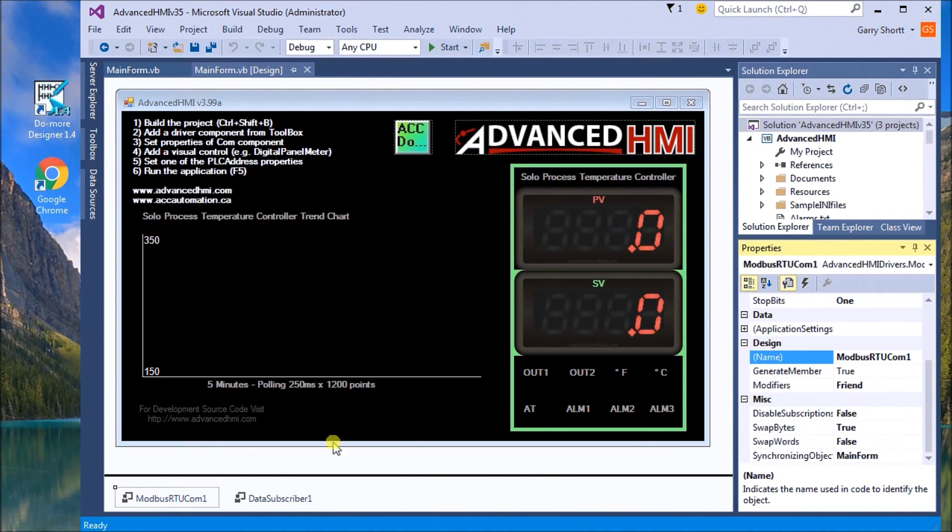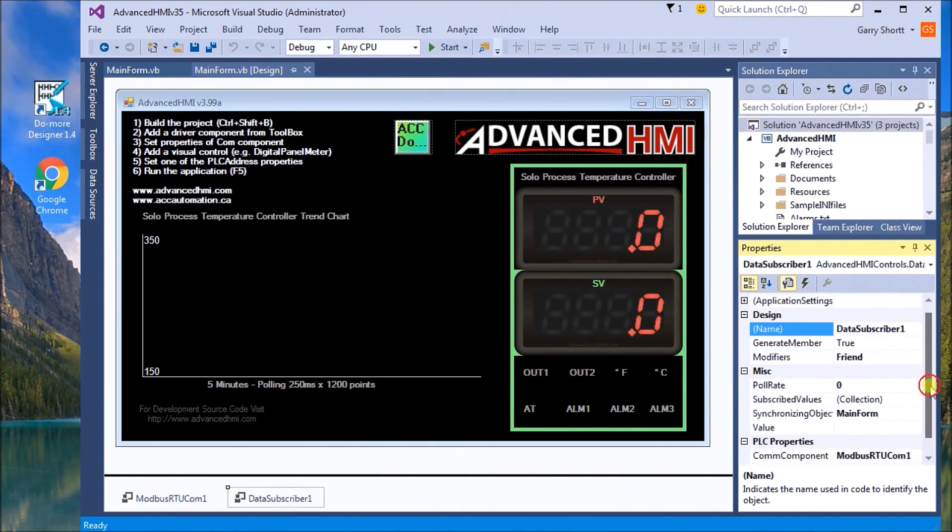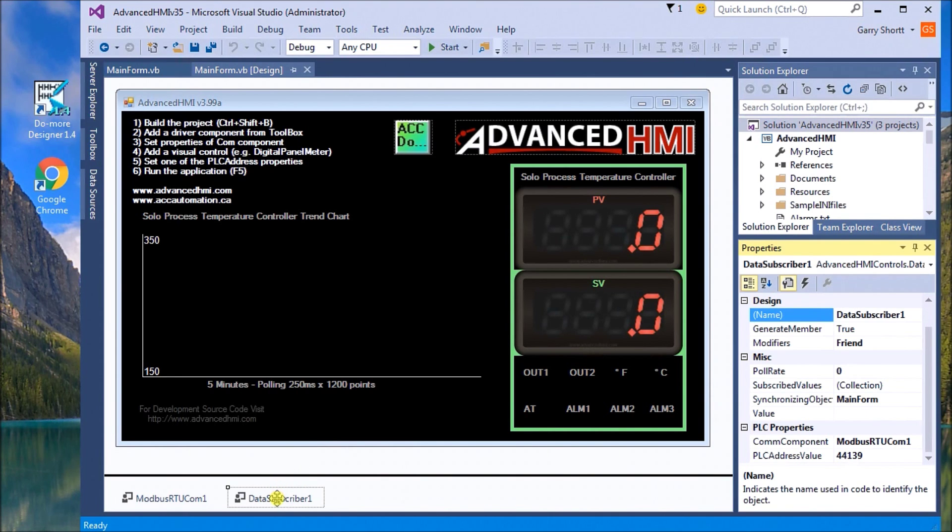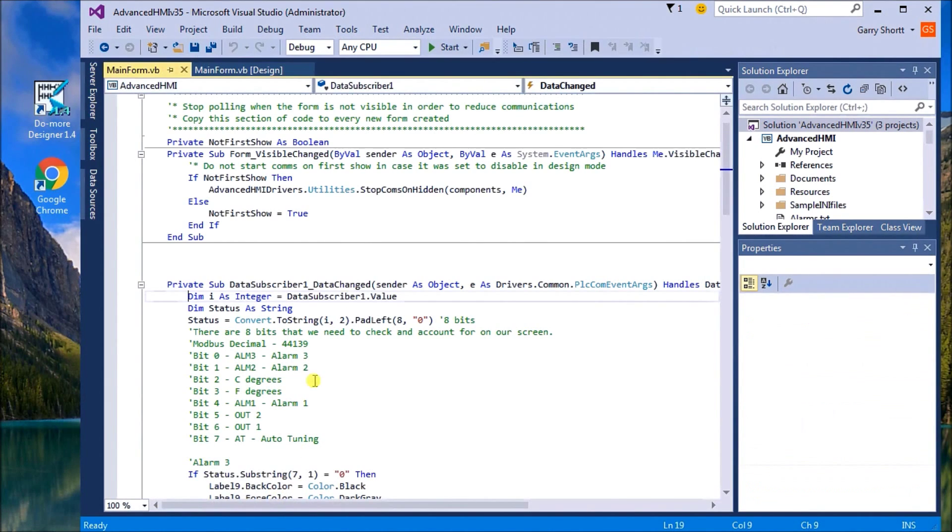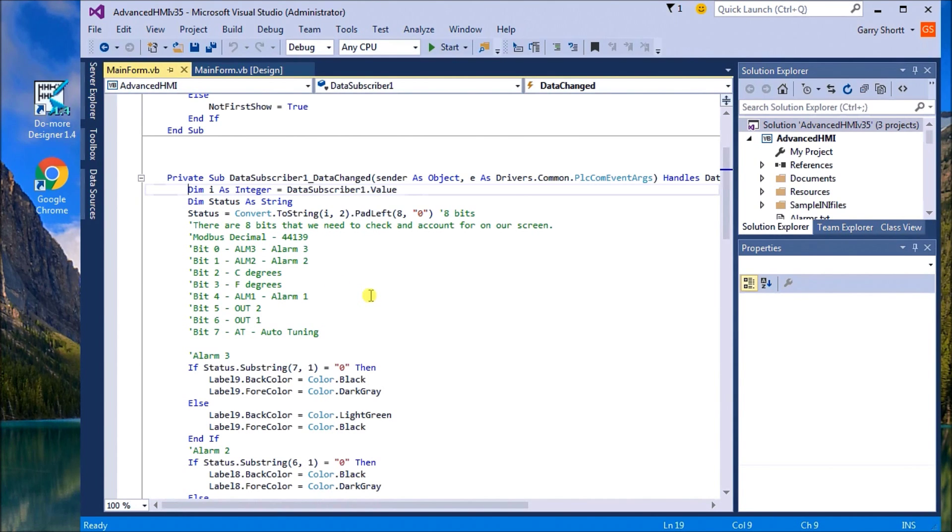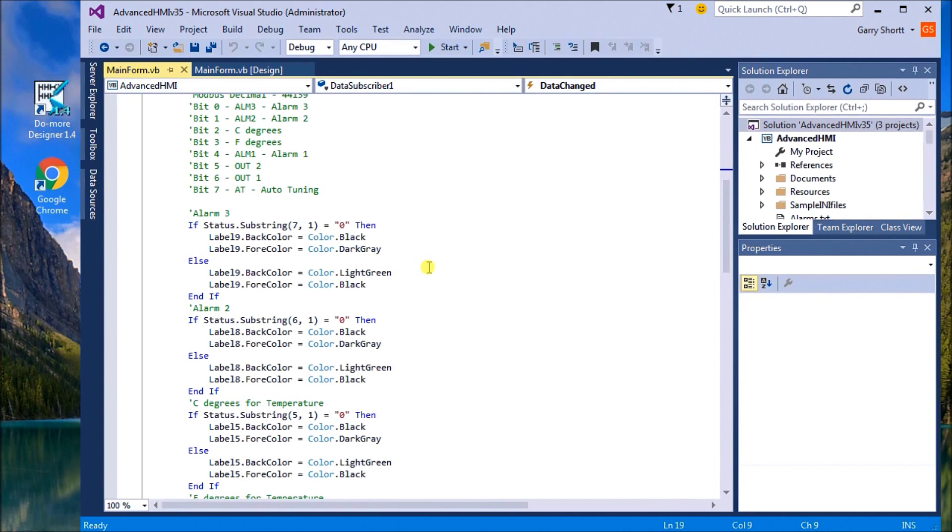Our data subscriber, this is where we're getting our bits from, PLC address 44139. What we do is we grab those eight bits and convert it to a string of zeros and ones to represent which bits are on. We look at each individual status of the string, and if it's a zero we change the background color, if it's a one we change the background color to another color.